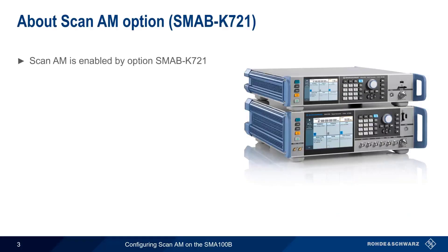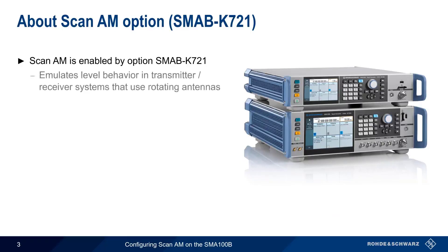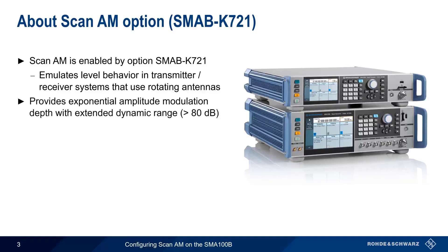On the SMA-100B, Scan-AM is enabled by software option K721. This option can be used to emulate the combined pulse and AM signals that we looked at a few moments ago. To do this, the SMA supports so-called exponential amplitude modulation, which can provide the extended dynamic range needed in these types of scenarios. Note, too, that either internal or external modulation sources can be used.